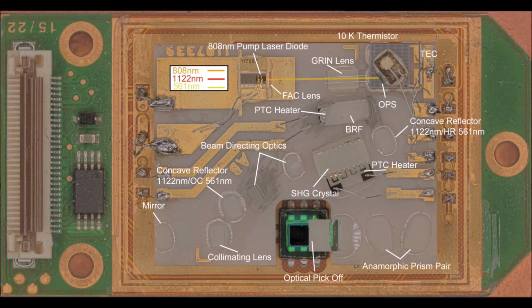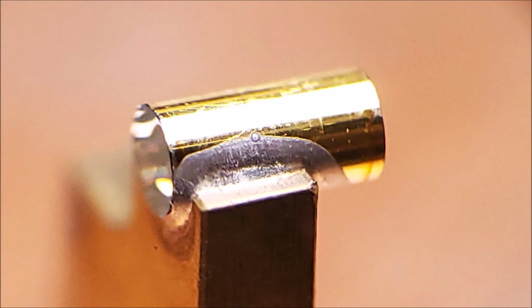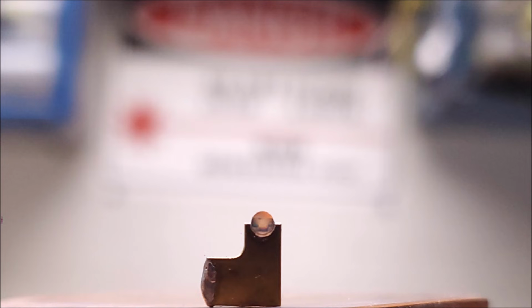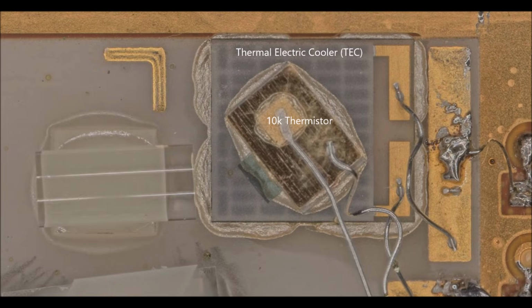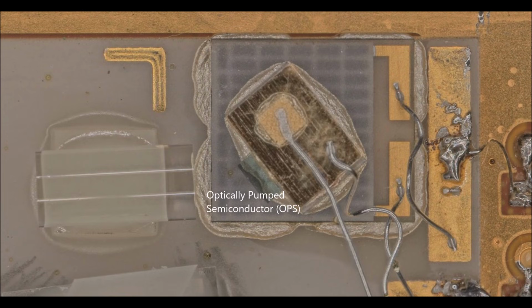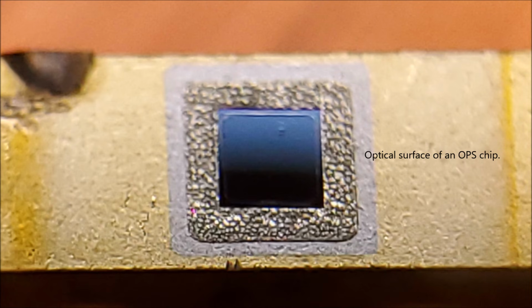The laser light is then focused onto a point using a GRIN lens. GRIN lenses don't work on physical geometry, but instead use a density gradient. The material in the center of the cylinder is denser than that of the material around the outer sidewall, which is metal plated. The term GRIN is short for gradient index, and it's a clever way to make small optics. The focused 808 nanometer laser light then hits the surface of the optically pumped semiconductor. These are specially tuned semiconductor lasers, but instead of being electrically excited, light is used for pumping the semiconductor gain material. For 561 nanometer production, the OPS converts 808 nanometers into 1122 nanometer laser light.